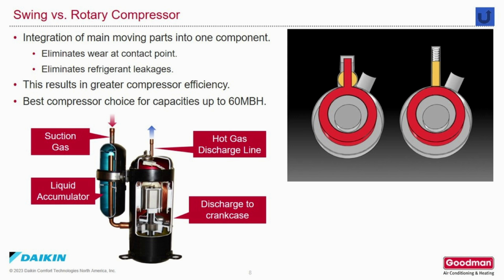The swing compressor versus the rotary compressor. Daikin has integrated the main moving parts into one component. That eliminates wear at the contact point and it eliminates refrigerant leakage. That results in greater compressor efficiencies. It is the best compressor choice for capacities up to 5 tons.